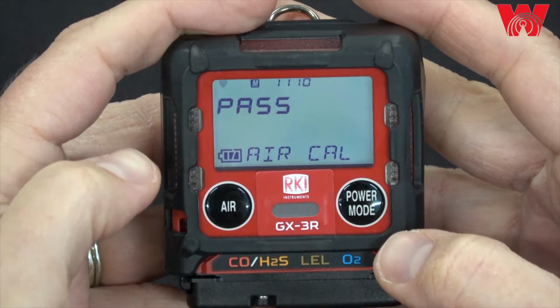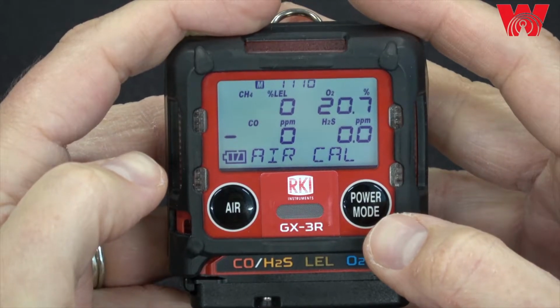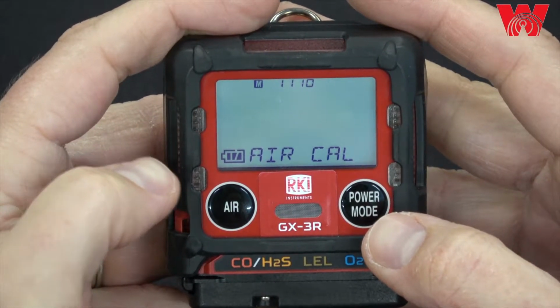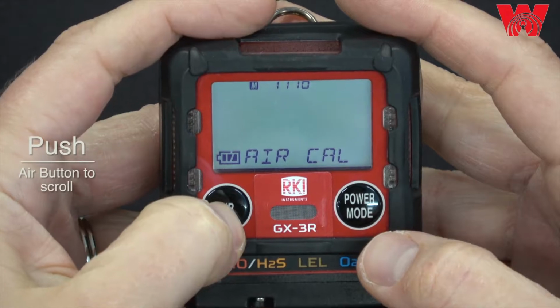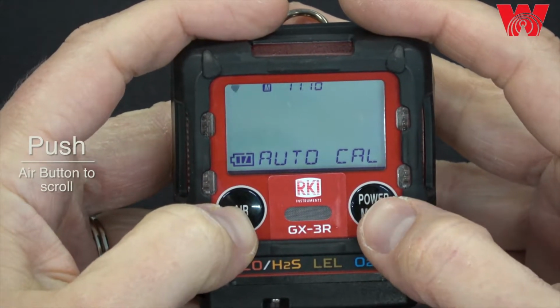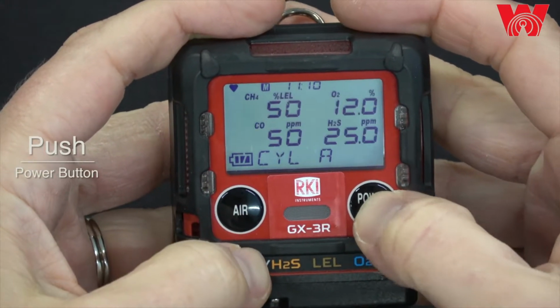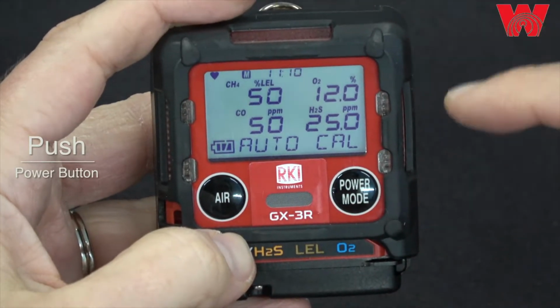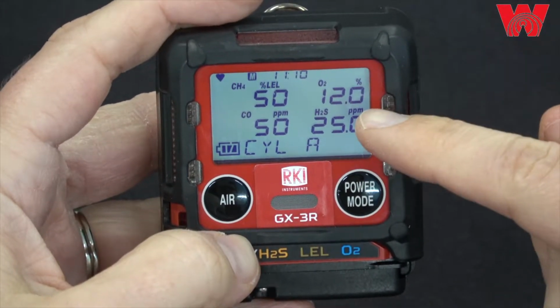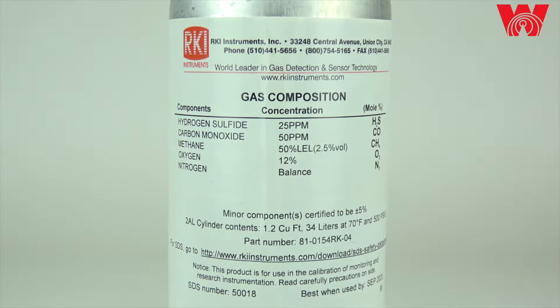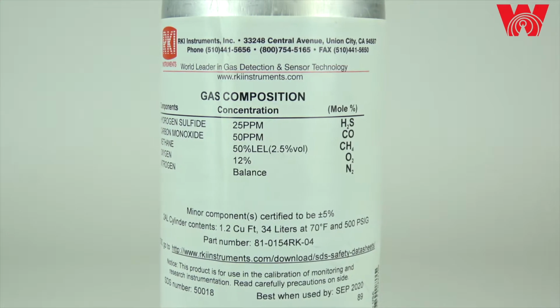The air cal was successful. These are the current readings. And now we need to scroll using air to auto cal, power mode to enter that menu. These are my auto calibration values. They need to match the values listed on your calibration gas cylinder.